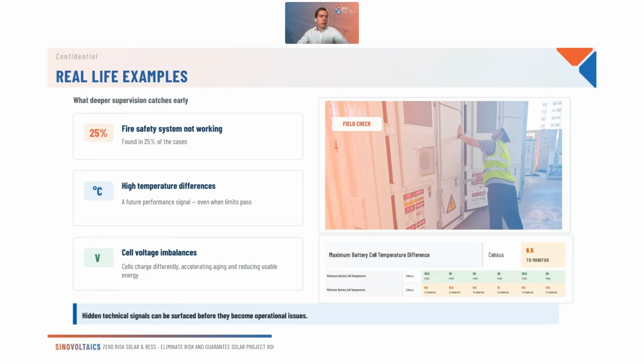And cell voltage imbalances—we also see this quite often with our software, meaning that when you charge or discharge the batteries, some of the cells will reach their threshold voltage faster than others. That will result in aging differences between the cells and modules, and also you will get less available energy out of the system, since some of them will start or stop earlier.